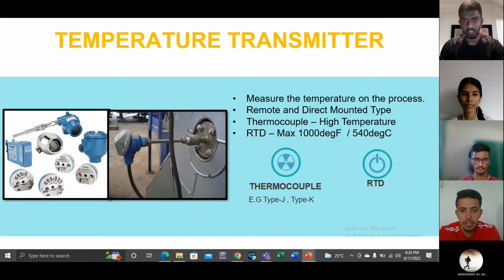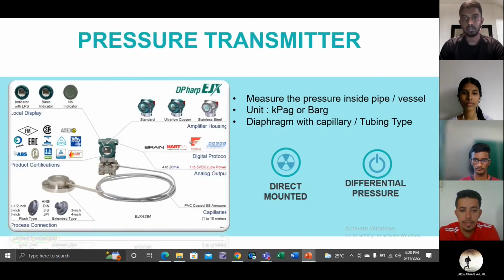So this is the temperature transmitter. The temperature transmitter just measures the temperature of the process. Remote and direct mounted type, thermocouple, high temperature RTD, maximum is 1000 degrees Fahrenheit or 540 degrees Celsius. Next is the pressure transmitter. The pressure transmitter measures the pressure inside the pipe or vessel. The unit used is kPag or barg, diaphragm with capillary or tubing type.